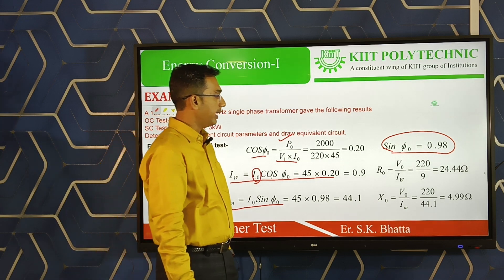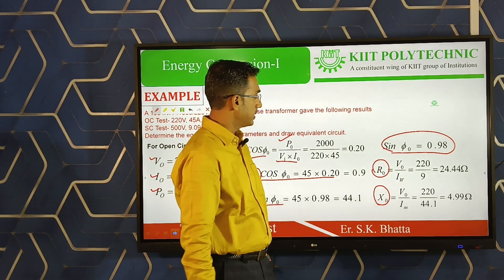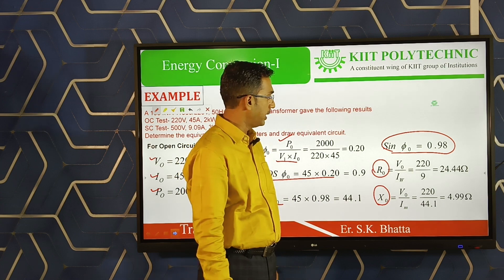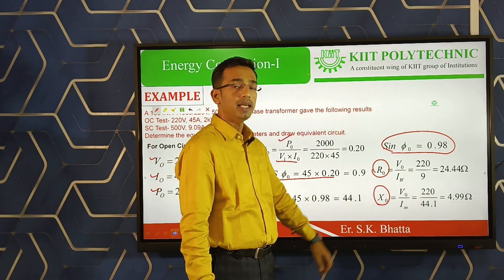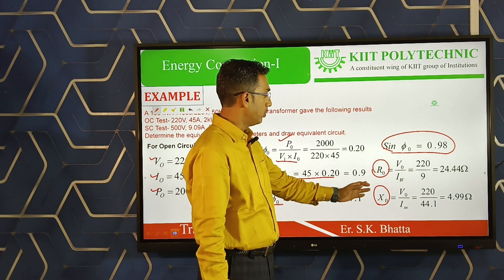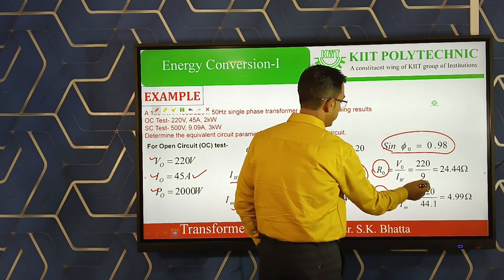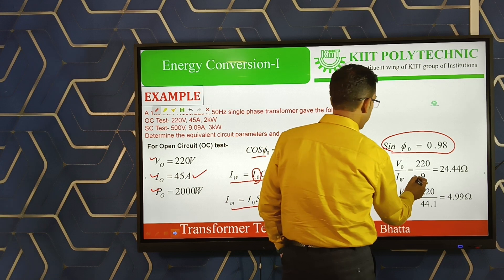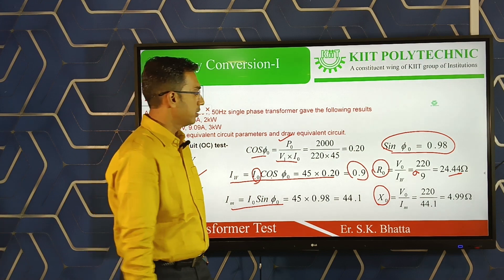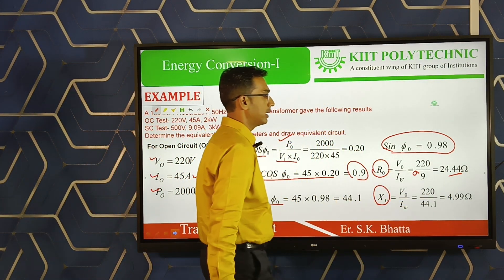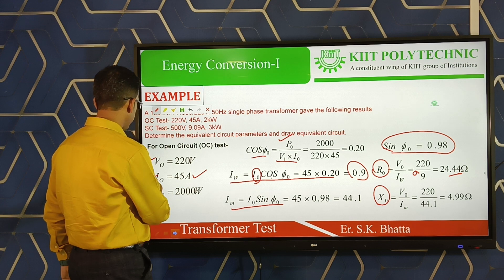With Iw and Im calculated, we find the shunt parameters: R₀ = V₀ / Iw = 220 / 9 = 24.44 Ω (approximately). X₀ = V₀ / Im = 220 / 44.1 = 4.99 Ω, approximately 5 Ω. These are the equivalent circuit parameters obtained from the open circuit test.